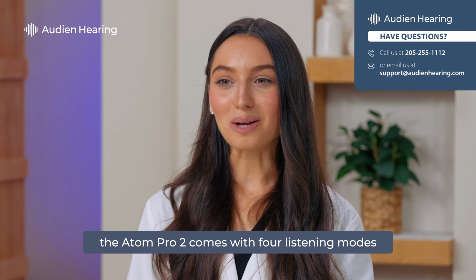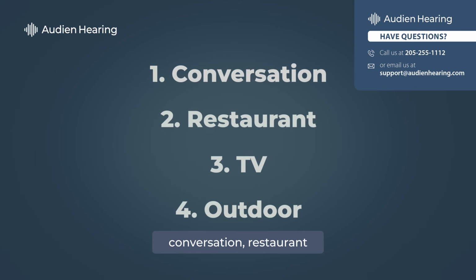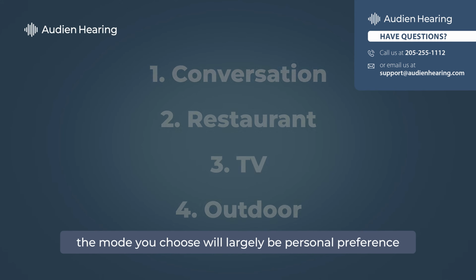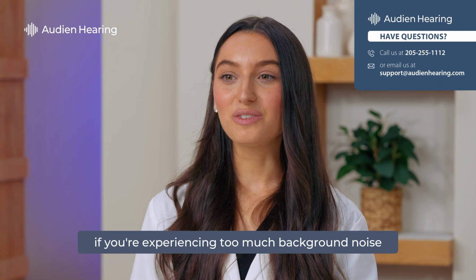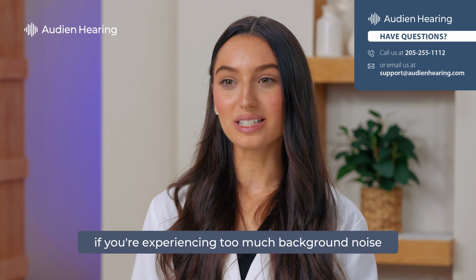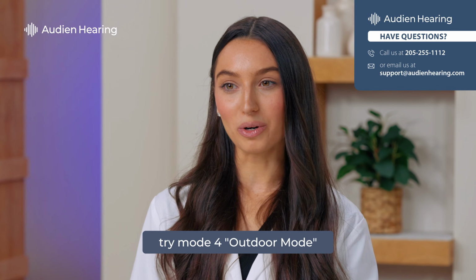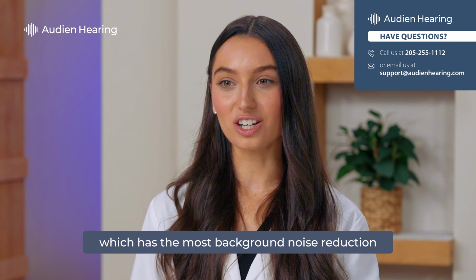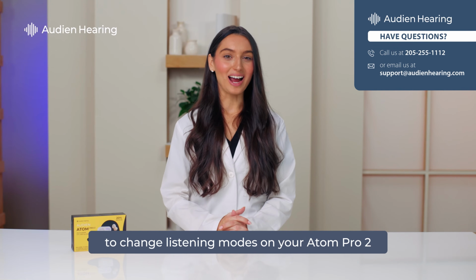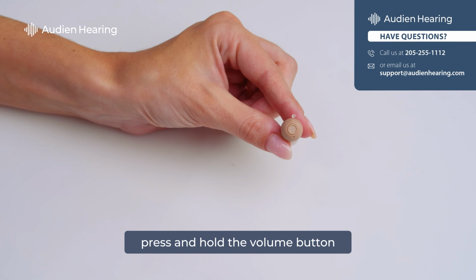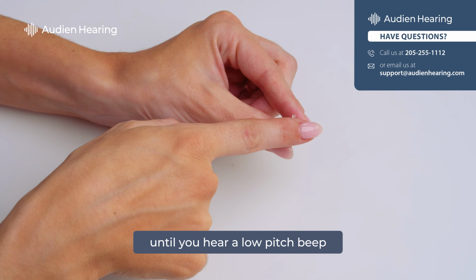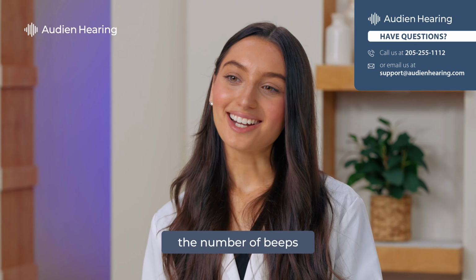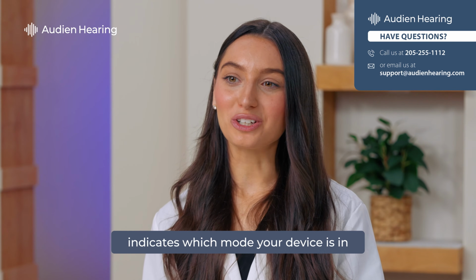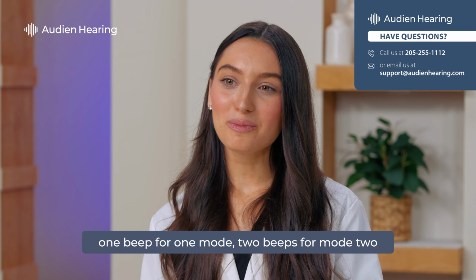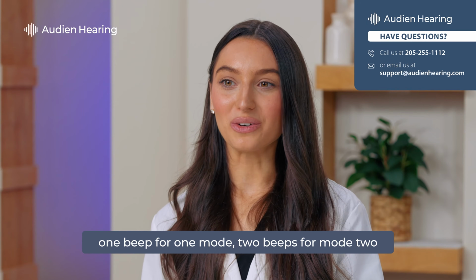The Atom Pro 2 comes with 4 listening modes: conversation, restaurant, TV, and outdoor. The mode you choose will largely be personal preference. If you're experiencing too much background noise, try mode 4, outdoor mode, which has the most background noise reduction. To change listening modes on your Atom Pro 2, press and hold the volume button until you hear a low-pitch beep. The number of beeps indicates which mode your device is in. 1 beep for mode 1, 2 beeps for mode 2, and so on.